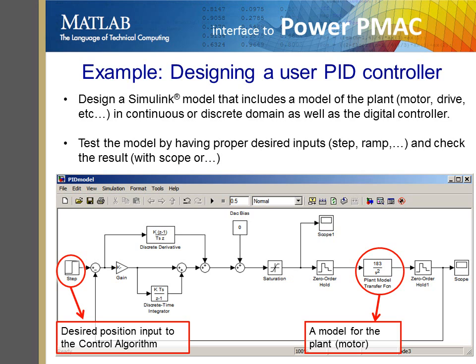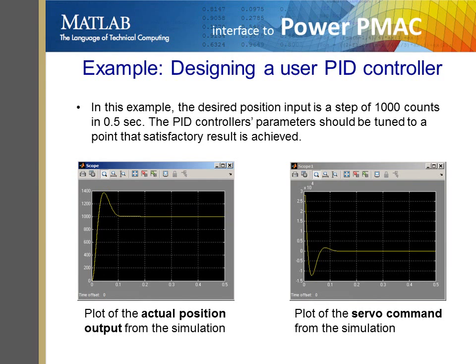Here is a quick example showing how one can design a PID controller with Delta Tau's MATLAB interface and deploy the generated code on PowerPMAC. The user needs to design a model in Simulink for their specific application. In this example, the Simulink model is using a step input as the desired position input to the PID algorithm, which is running as a simplified model of the plant or the electric motor. Here are simulated position input and servo command responses from Simulink.